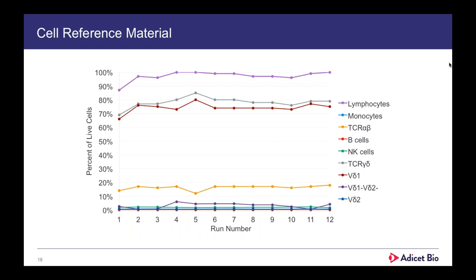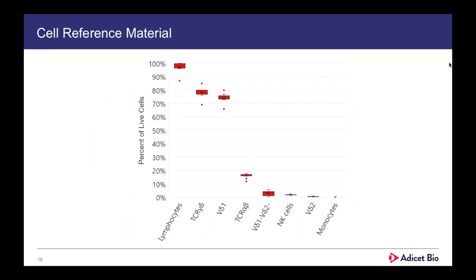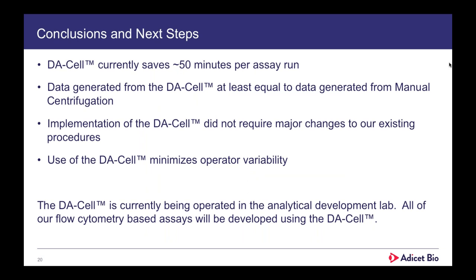This slide shows reproducibility of reference material over time. We use a frozen bank of cells that we can thaw for every single run. Over 12 runs spanning almost four months, the relative frequencies of each subset, while there's some fluctuation, are fairly consistent across the board. This is completely independent runs with completely independent users running the analysis, and still we maintain consistent percentages of each population. Compiling this data as a box-and-whisker plot, you can see very tight specs. We can develop an internal certificate of analysis for our reference material so we know exactly how well our flow cytometry panel is performing — highlighted by the optimization we got with implementation of the DA cell.